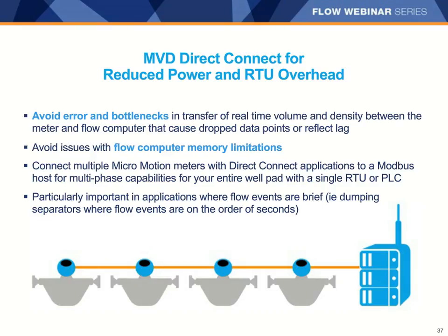This is particularly important because if you were to try to do these calculations in the RTU or flow computer, you can miss volume, particularly with separators that have dump valve actuation. When I think of many of the customers that I've visited, the cycle of their dumps only occurs for a few seconds at a time. So if you miss a few data points, your calculation can get off significantly if you're relying on that RTU.